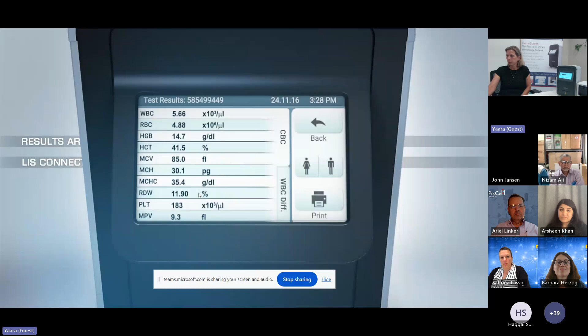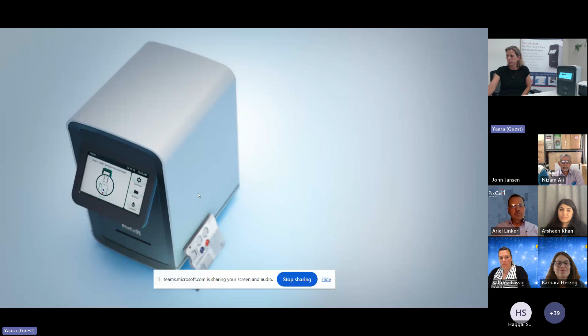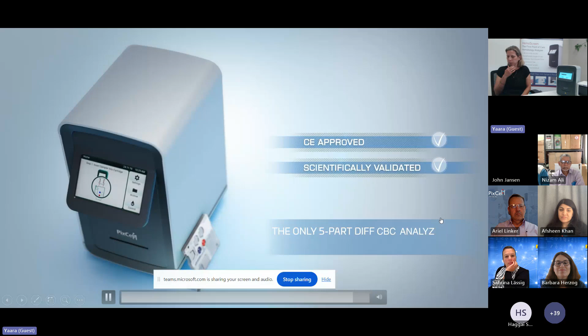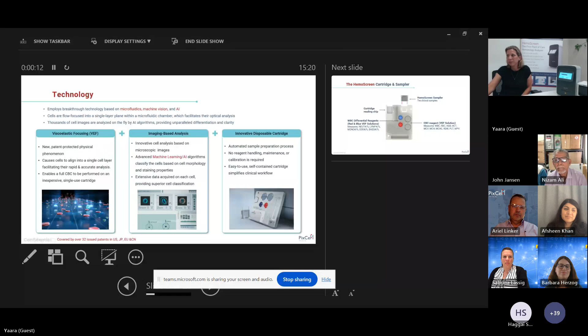During the insertion of the cartridge, the blood sample is expelled from the capillaries into the reagent chambers. It is then mixed with the liquid reagents via actuators pressing on the pressable portions of the chambers. Once mixed, a seal bursts and the resulting suspension flows into a buffer chamber, and from there into a microfluidic chip. PixCell's revolutionary technology is based on a patented method called Viscoelastic Focusing. Viscoelastic Focusing causes cells to form a single cell layer, facilitating their optical analysis. The blood flows through a microchannel while cells focus at the center and form a single layer plane. Images of the focus cells are analyzed using cutting-edge machine vision algorithms.